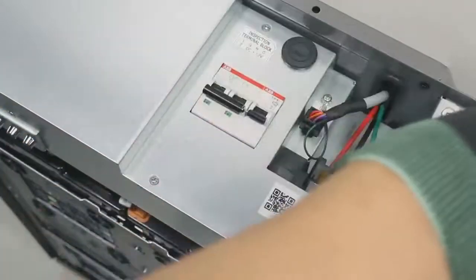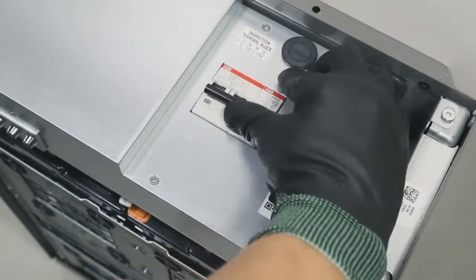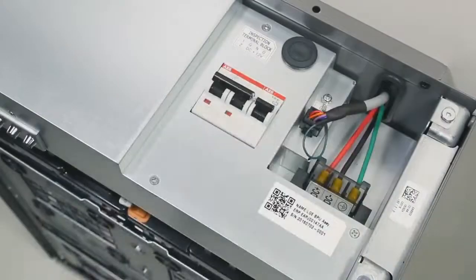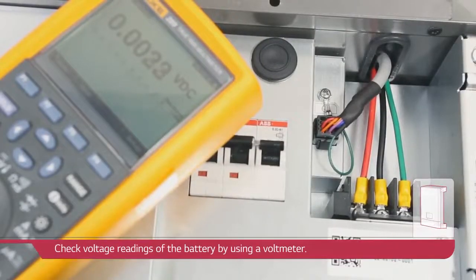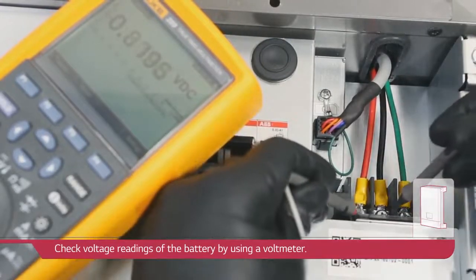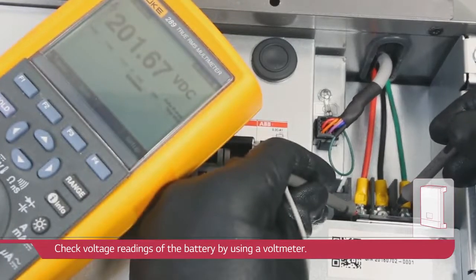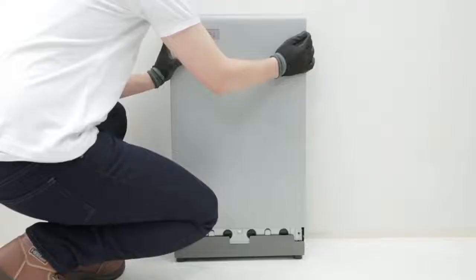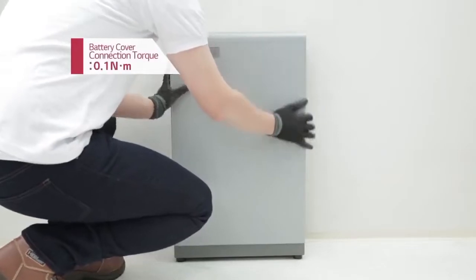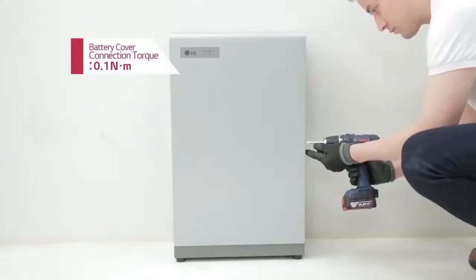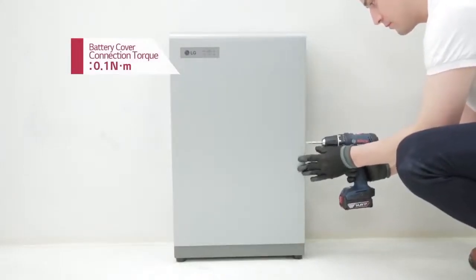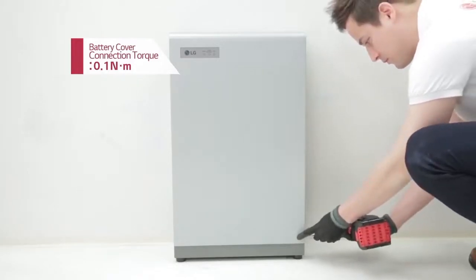Take the seal off the safety label and turn on the DC circuit breaker on the BMS board of the battery pack. Check voltage readings of the battery by using a voltmeter. If the voltage is not within the normal range, contact an authorized dealer. Assemble the front cover of the battery by sliding it down and fasten the screws on both sides of the battery pack after closing the front cover.